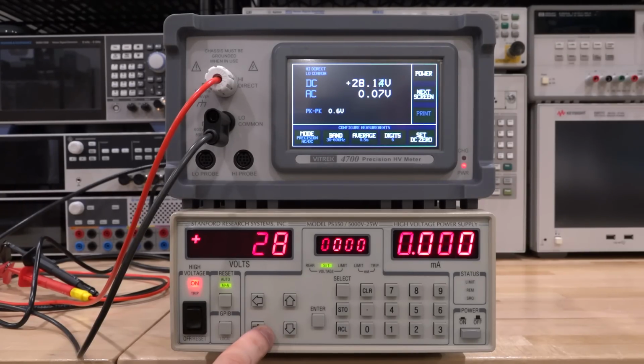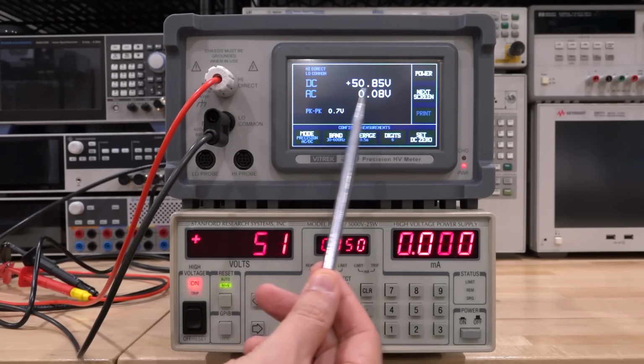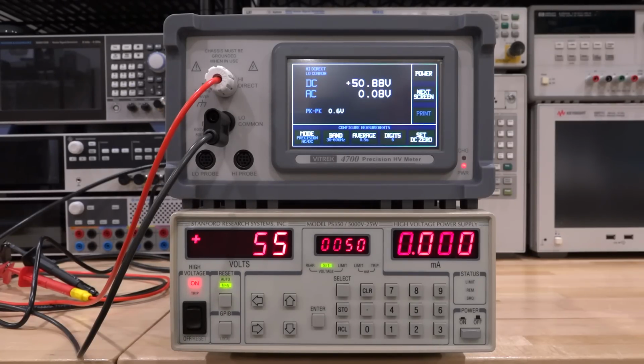So if I go over here, for example, and ask for 50 volts, it should stabilize nicely to 50 volts. Man, that's a reasonably good job. Look at that, it jumps around a lot, but you know, it's fairly stable at the output. So let's take a look at the circuitry and see how this instrument actually works.